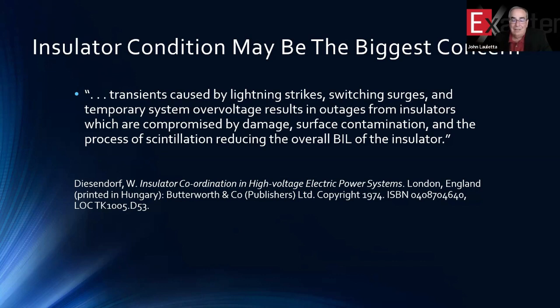And now that insulator is going to be the one that flashes over during a transient event like a switching surge or a lightning surge. And when the lineman goes out and the circuit's dead and he doesn't see any dead animals laying on the ground, there's no trees touching the wire, he comes to the point of, I don't know what's wrong, and he'll slam a fuse in or reclose an operating switch, and everything holds. Well, that's because the flashover burnt off those dry bands from the high energy event on that insulator, and that resulted in the insulator kind of going back to more of its normal condition and holding.